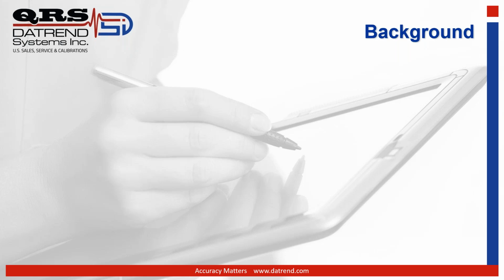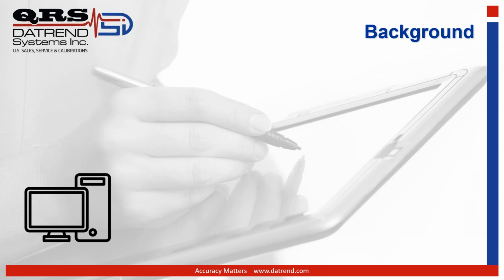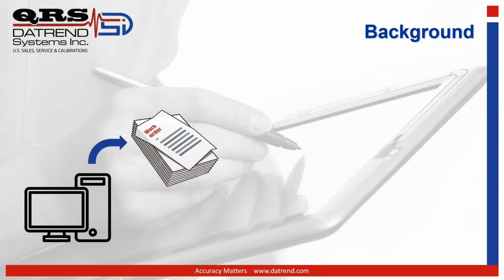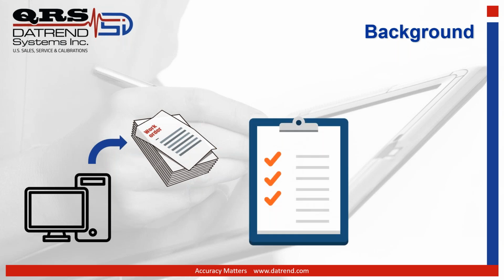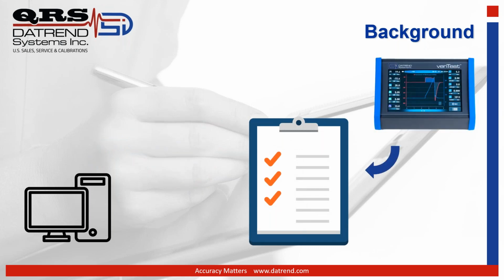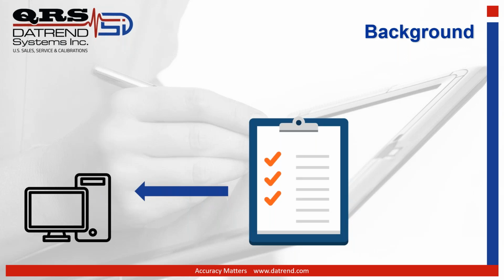But despite the technological advantages, the vast majority of CMMS-enabled hospitals are doing a ton of manual entry. Their day might actually look like this. First, someone would generate work orders created in the CMMS software. They take paper printouts of their test reports, often photocopied. Then they would have to test with their analyzers and simulators and fill in the results as they go. Finally, at the end of the day, our techs are re-entering their test results of each measurement from paper copy back into a computer to close out those work orders.